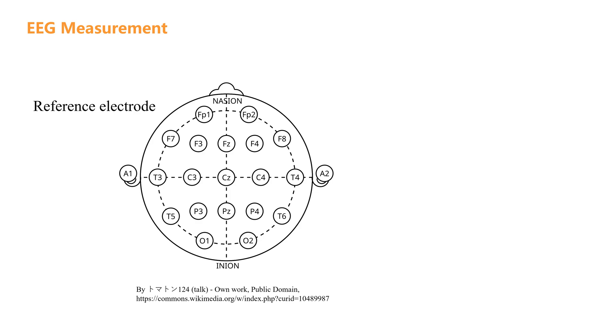The reference electrode provides a baseline, helping us interpret brain activity more accurately. So which electrodes can be used as reference electrodes? Common reference electrodes include CZ, linked ears, linked mastoids, ipsilateral ear, contralateral ear, and nasion.